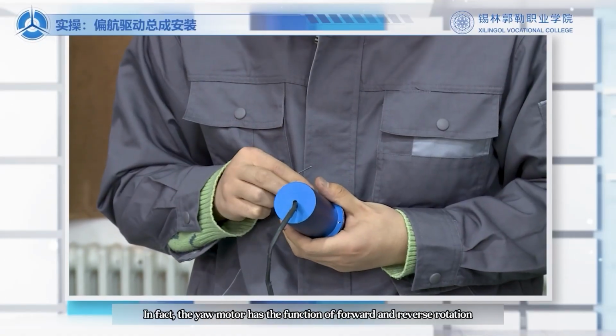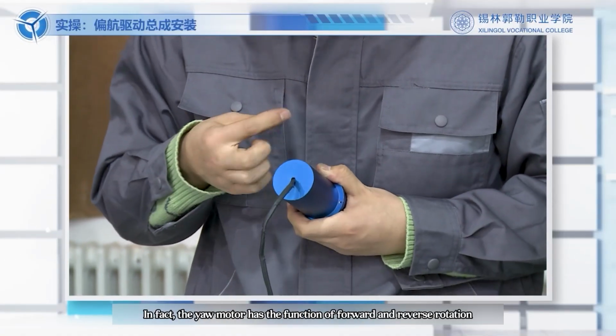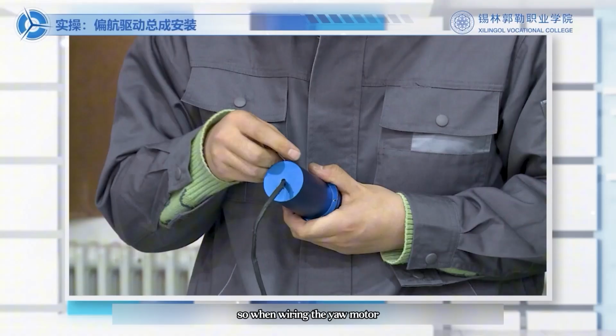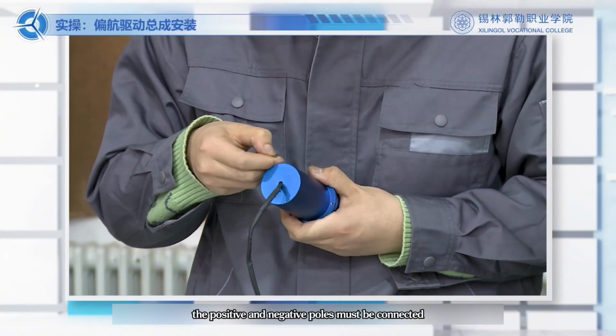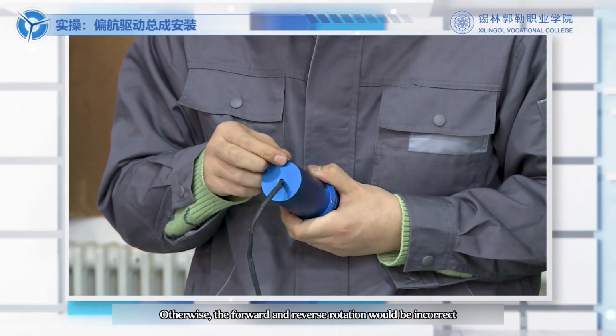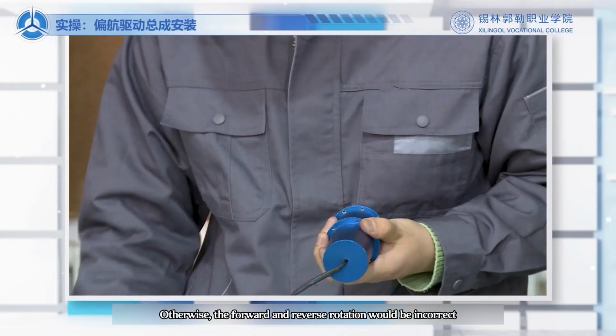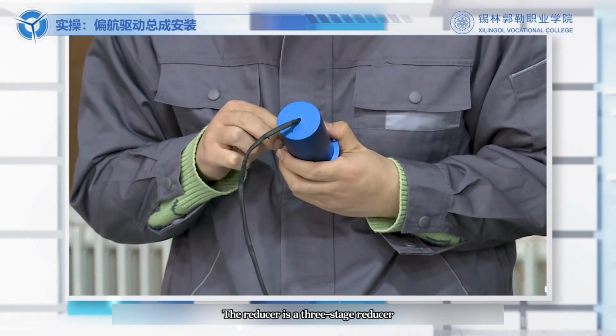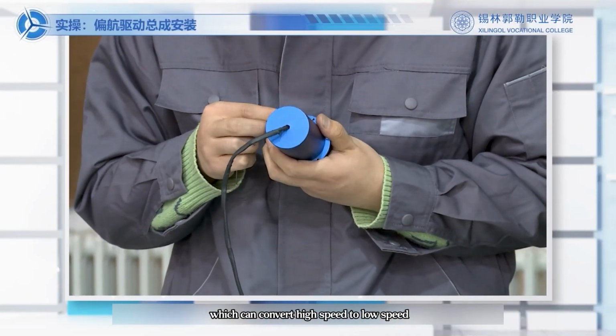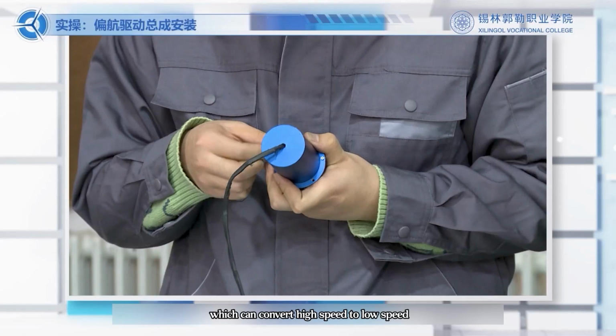In fact, the yaw motor has the function of forward and reverse rotation. So when wiring the yaw motor, the positive and negative poles must be connected. Otherwise, the forward and reverse rotation would be incorrect. The reducer is a three-stage reducer, which can convert high speed to low speed.